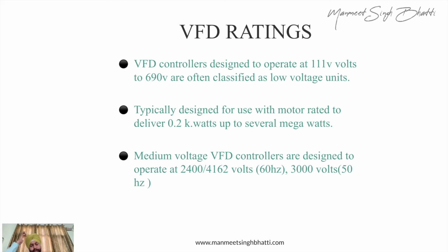Plus, we can get you 0.2 kilowatt as the lowest rating, and then you can go up to some megawatts. So if you need 5 megawatt or 6 megawatt motors on low voltage 690 volts, it can be done. Then the next VFDs are medium voltage. Medium voltage is basically for the high-end motors, mostly going to crushers, cement plants, quarries. There we use them.